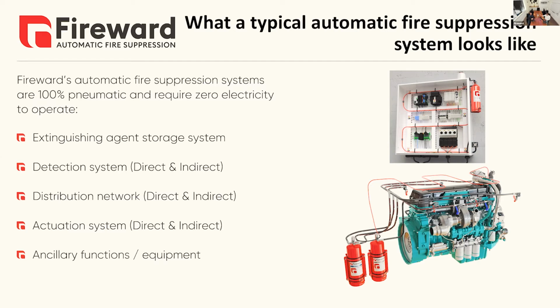You have a detection system. This is available in direct and indirect, the two technologies. The top image there with the small cabinet is the direct. The tube is routed around the risk. Where there's heat, there's activation, and discharge directly where that heat source is, so it's in communication with the cylinder directly. However, in indirect, the detection tube has a pressure loss when it heats up, which in turn opens a valve and delivers the fire suppressing agents through a discharge network and nozzles. In summary, the direct systems that you see in the control panel are for small, localized environments, and the system that you see below is for much larger environments, like engine bays of heavy equipment.